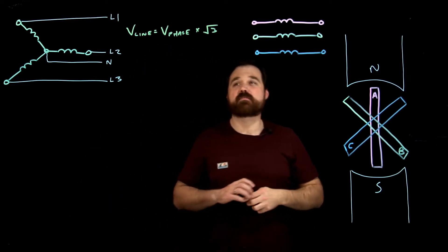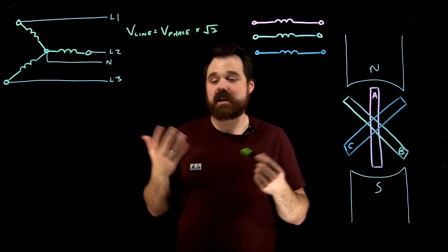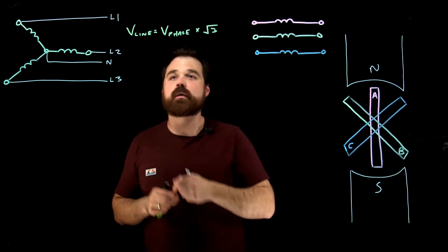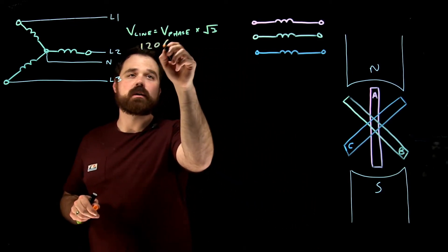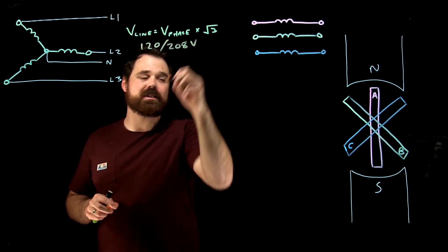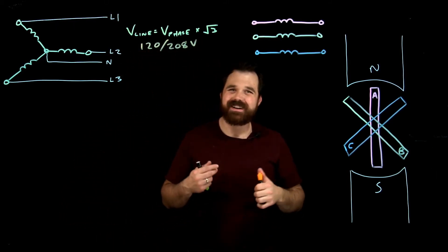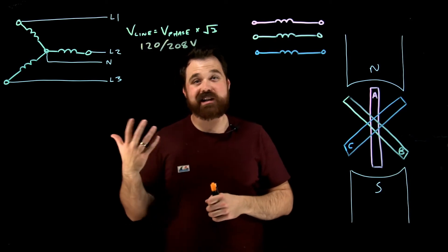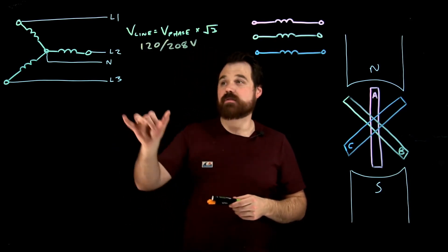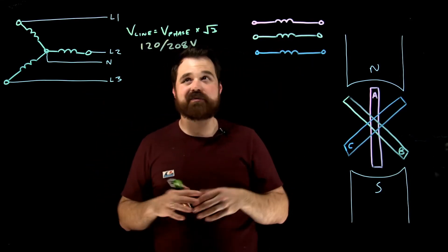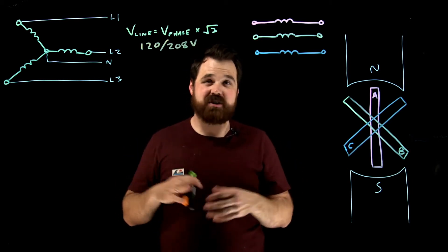All right, so we have that ability to have a higher line voltage. And in this case, if we were using 120, we would have a 120/208 volt system. So our voltage has the ability to be root three larger. Now, so the phase is still rated for that same 120 volts and whatever that current is.